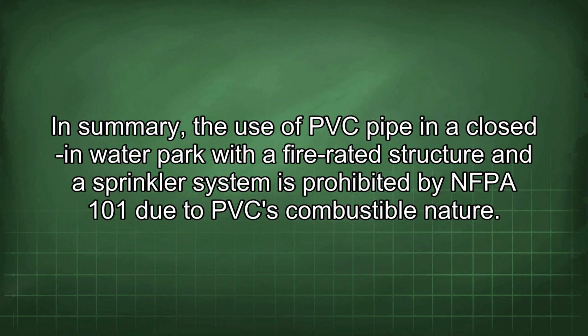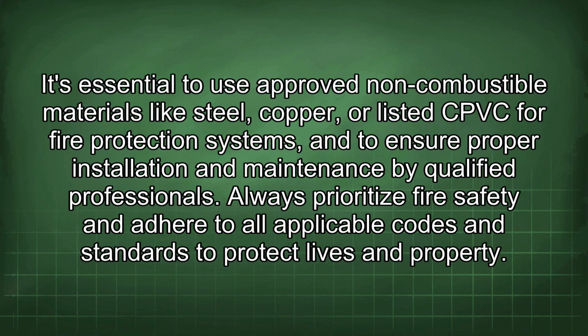In summary, the use of PVC pipe in a closed-in water park with a fire-rated structure and a sprinkler system is prohibited by NFPA 101 due to PVC's combustible nature. It's essential to use approved non-combustible materials like steel, copper, or listed CPVC for fire protection systems, and to ensure proper installation and maintenance by qualified professionals. Always prioritize fire safety and adhere to all applicable codes and standards to protect lives and property.